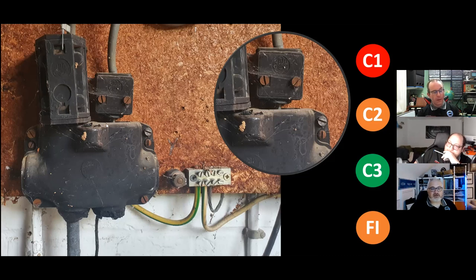So I'm going to go C1 just because that's under a staircase, small child scenario. It may not meet the IP finger test. What's the risk here, for those who may not know? It's the live part within the circle where the neutral connection is. Okay, so reaching of the live parts. Yes. So for me, I'm going at a C1.